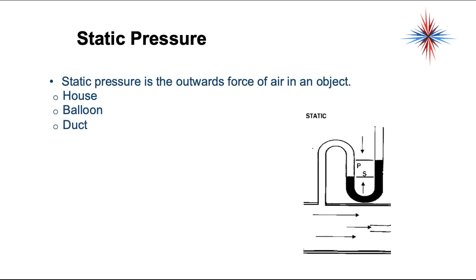Static pressure is the outward force of air in an object — could be a house, balloon, or ductwork. The static pressure is the measurement of the pressure coming out against the sides of the ductwork. It's measured in water column. So the outward force of air is static pressure.